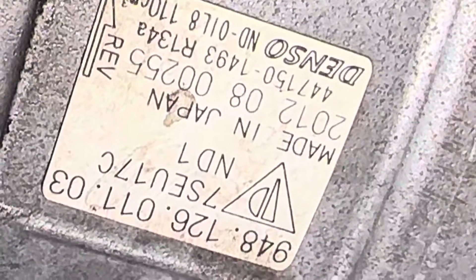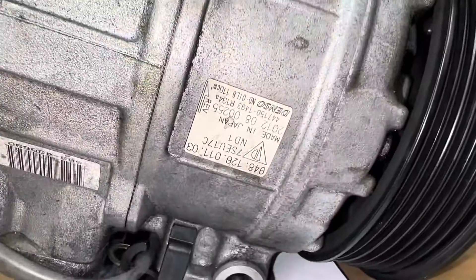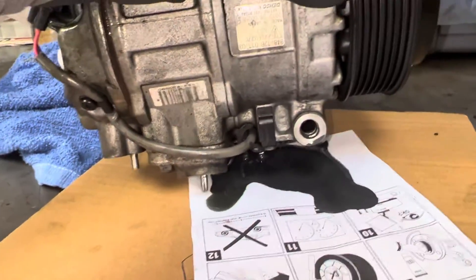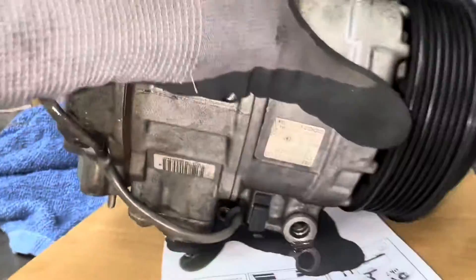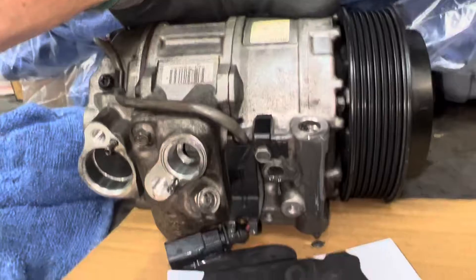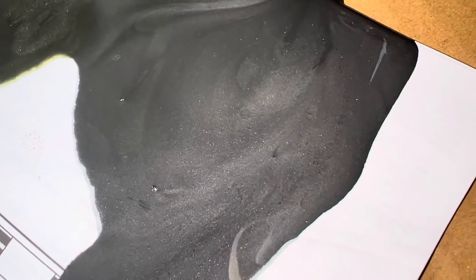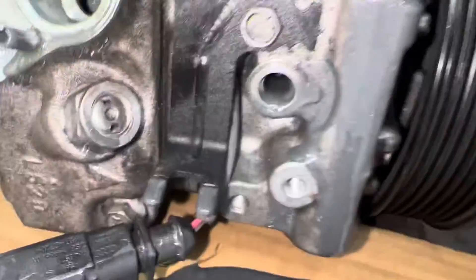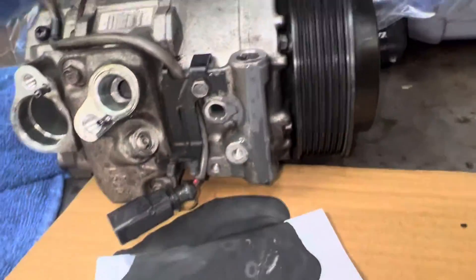All right, we got another learning experience. Yes, it is upside down. So let's zoom out and look at what we found. Remember in the other video, I mentioned there was a little bolt on there — I said it's an oil drain plug, because it is. And do you see this beauty? That metal flake — isn't that beautiful? Don't we love to see this stuck inside our system without flushing it? And that was from that hole right there with the oil drain plug.